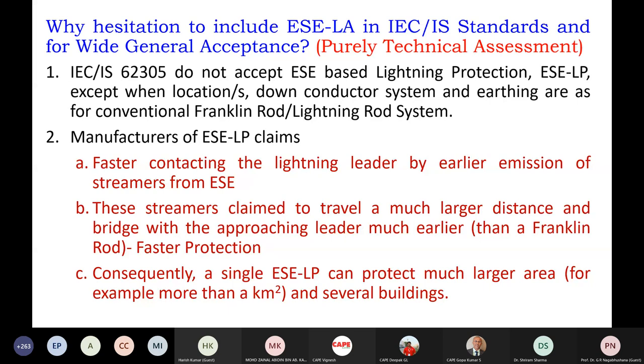And then, what are the claims of the manufacturers of the ESE? They say the streamer from the tip of the ESE moves very fast compared to the streamers from a Franklin rod, therefore it contacts the lightning leader earlier and therefore protects the surrounding area. These streamers are claimed to travel a much larger distance and bridge with the approaching leader much earlier than a Franklin rod. That means faster protection, larger area.